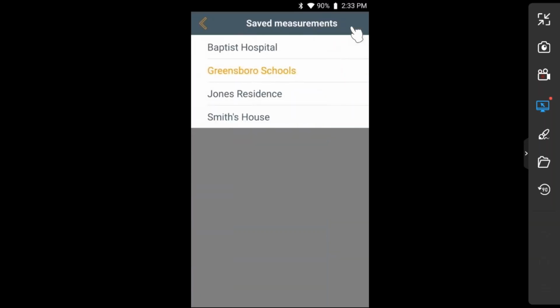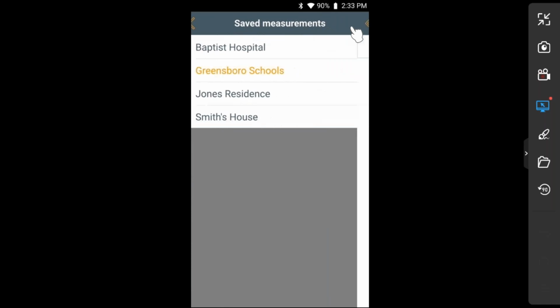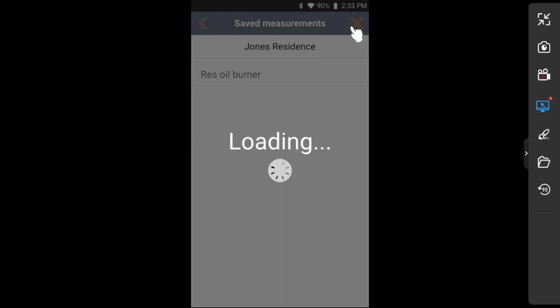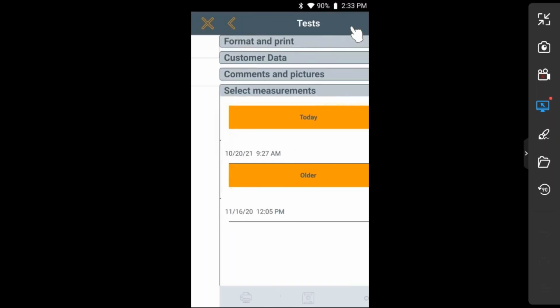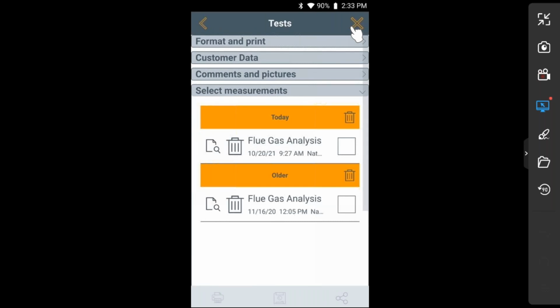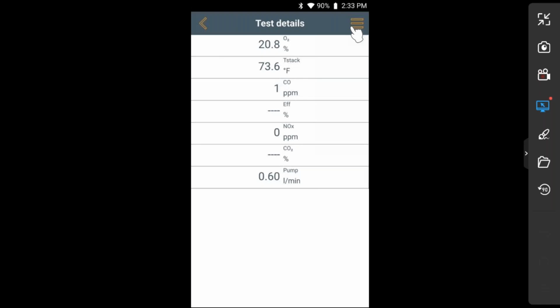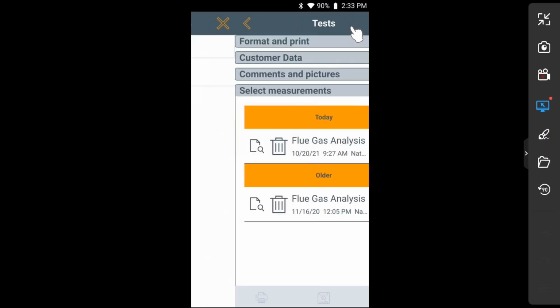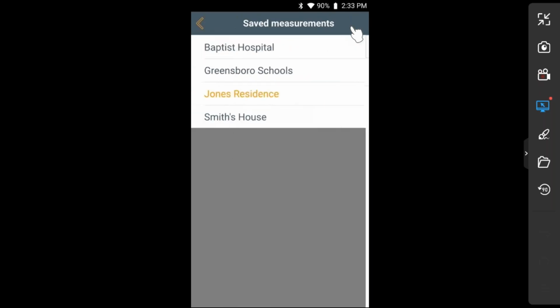Here are the tests that are stored in the instrument. I could go into, let's say, Jones Residence, where I have a residential oil burner, and pull that up and show the previous tests that I did over a period of time. You'll see here that on 1020, I did a test on a residential furnace, and there are my readings right there. You can keep thousands of tests stored on this analyzer. You're going to have a list of all these customer names on here, and after the customer name, you can go in.